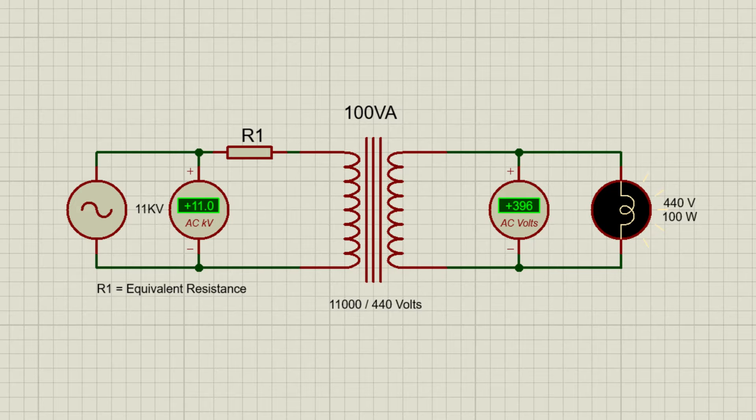Imagine a secondary winding rated at 440 volts that's fully loaded. If the measured voltage drop is 44 volts, then your percentage voltage drop is 10%. This translates to a transformer percentage impedance of 10%.